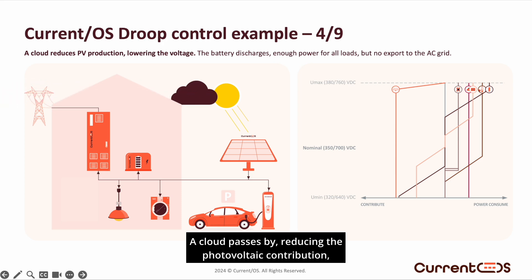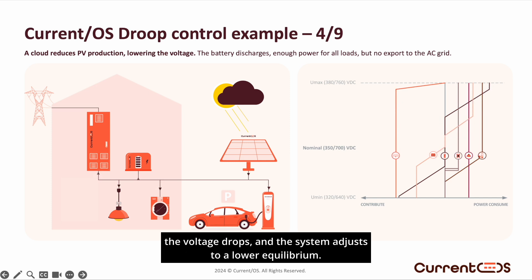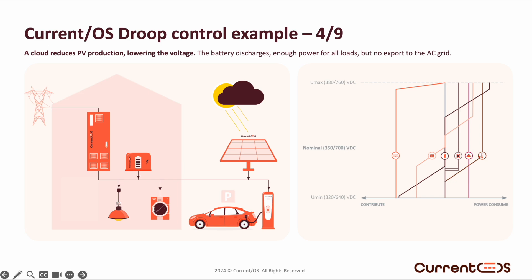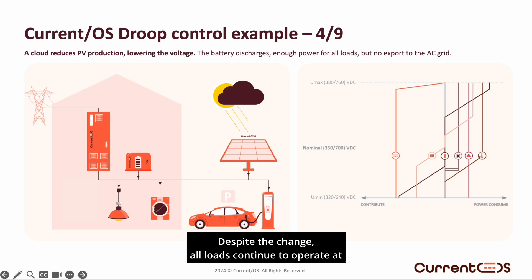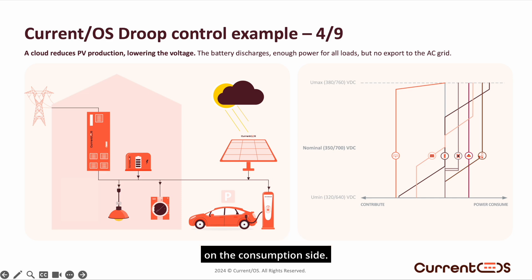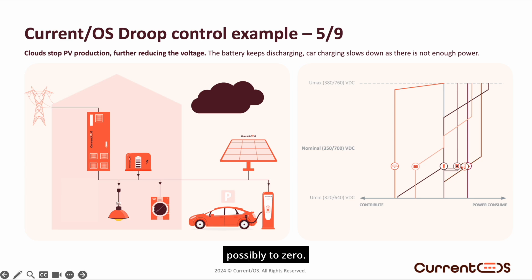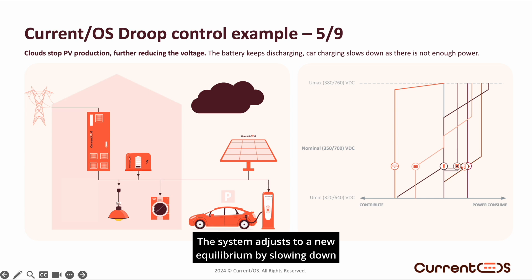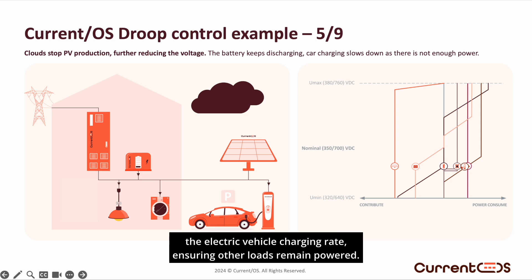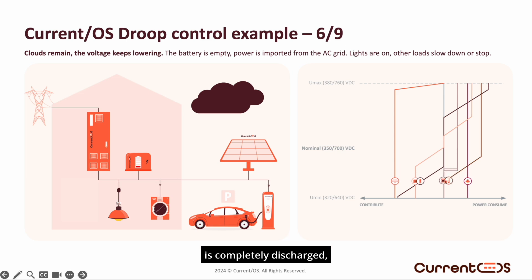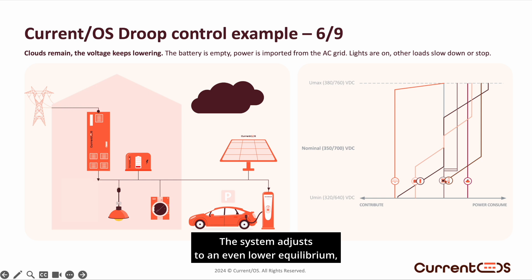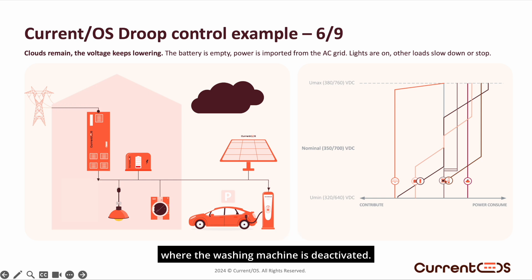A cloud passes by, reducing the photovoltaic contribution — the voltage drops, and the system adjusts to a lower equilibrium. At this new equilibrium, the missing power is drawn from the battery. Despite the change, all loads continue to operate at their nominal power, ensuring no disruption on the consumption side. More clouds arrive, further reducing the photovoltaic contribution, possibly to zero. The battery is pushed to its maximum output, but it's still not enough to power all the loads. The system adjusts to a new equilibrium by slowing down the electric vehicle charging rate, ensuring other loads remain powered. This situation can continue until the battery is completely discharged, at which point it stops contributing, and the system adjusts to an even lower equilibrium where the washing machine is deactivated.